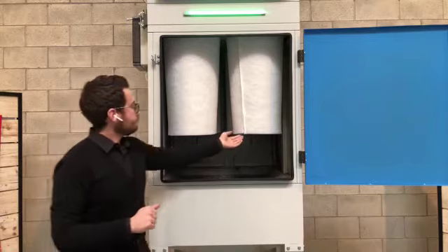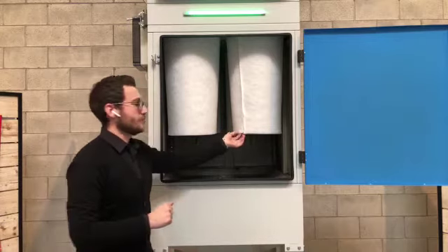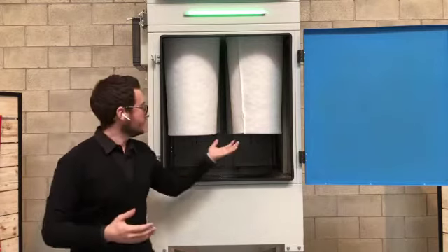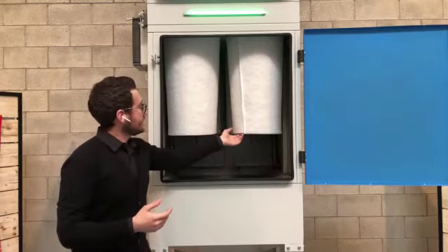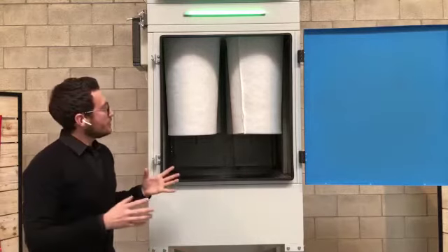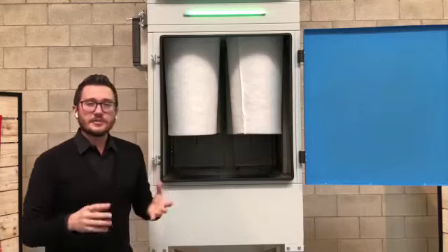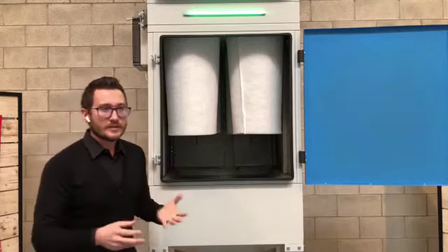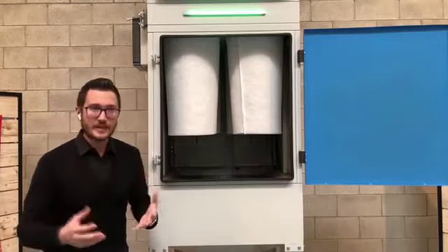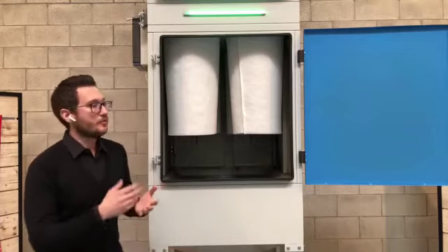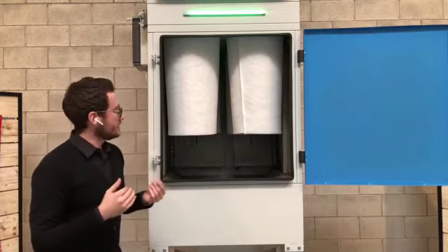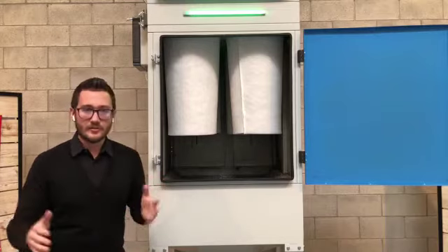Okay. Then the second one, which is obviously the core of the system, the heart of the filter, is the cartridge, which is in fiberglass. Okay. So we speak about a cartridge which gives you already a filtration that can be considered an absolute filtration, because we speak of a level of H11 filtration. So it is a really high filtration level.